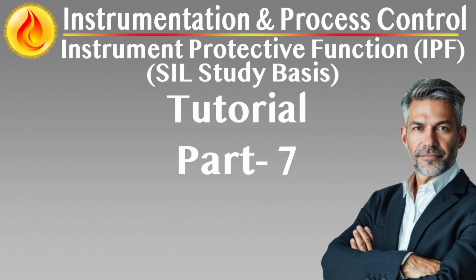Non-disruptive operation. Automatic testing must not interfere with the process or cause spurious trips. Functions must be designed to perform self-checks transparently during normal operating conditions. Alarm and fault handling. Any failure detected during automatic testing must trigger a diagnostic alarm or visual indicator. If the fault compromises the IPF function, compensating actions, e.g. trip, bypass escalation, or controlled shutdown must be initiated.